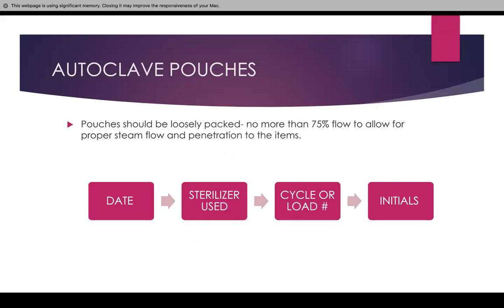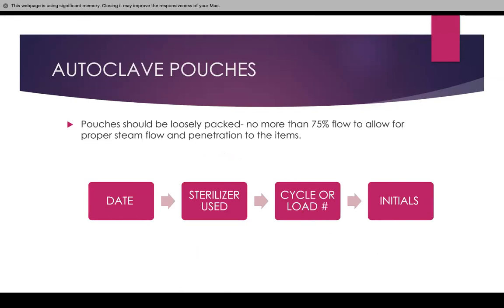For autoclave pouches, it's very simple. You have to have the date of when you enter it, the sterilizer used, the cycle or load number, and your initials. You cannot have one of these missing — you have to have all four pieces of information on it.